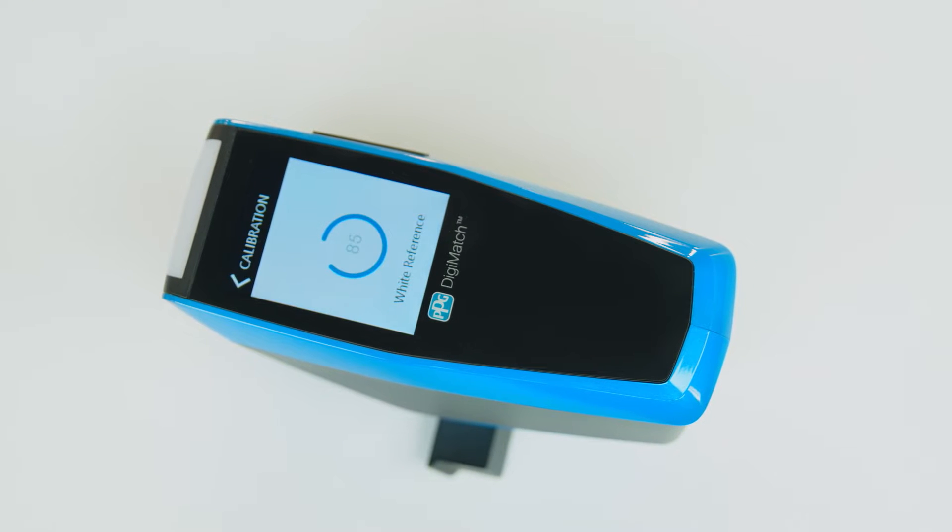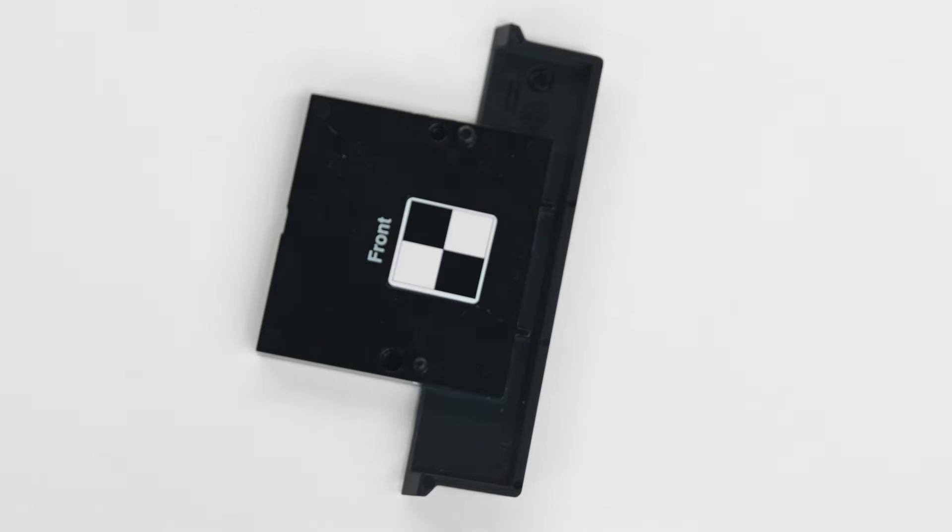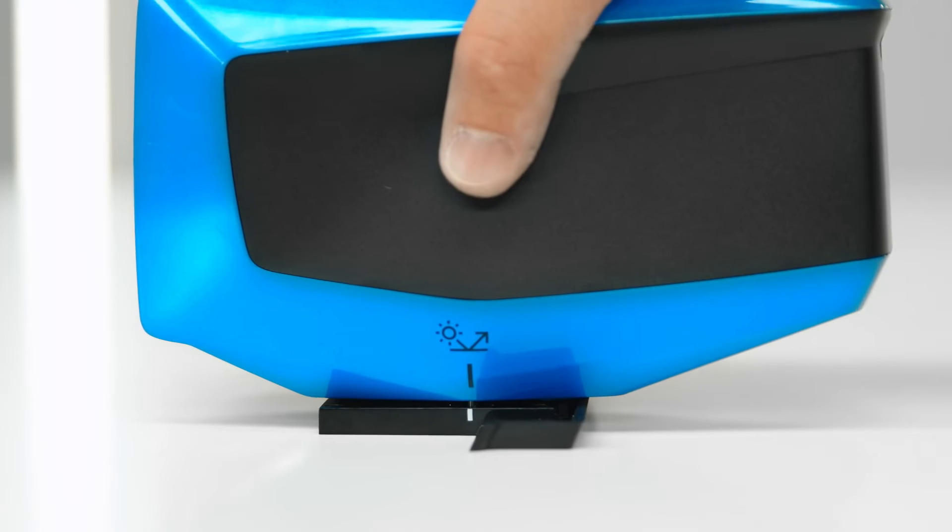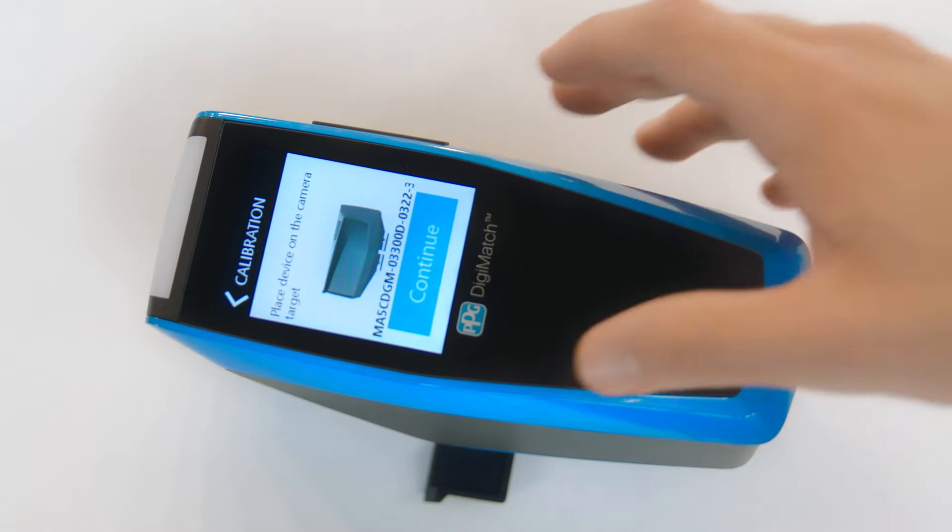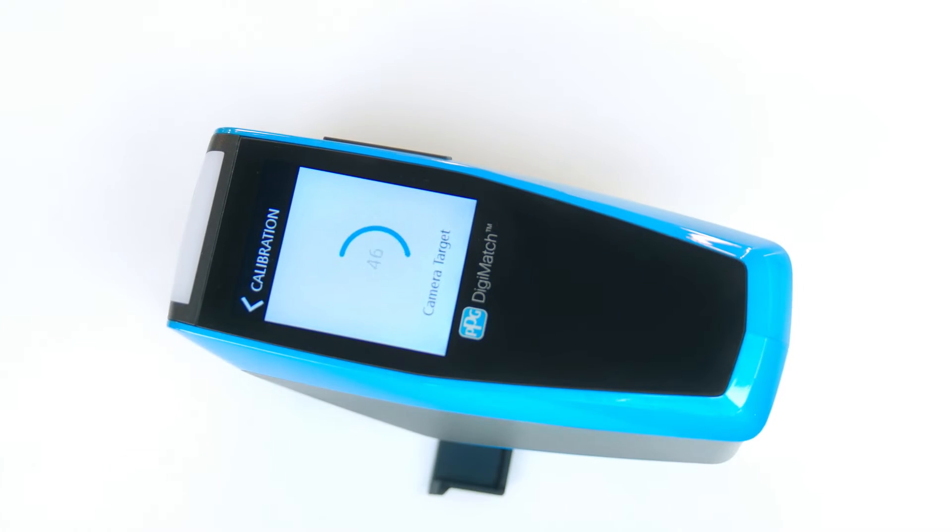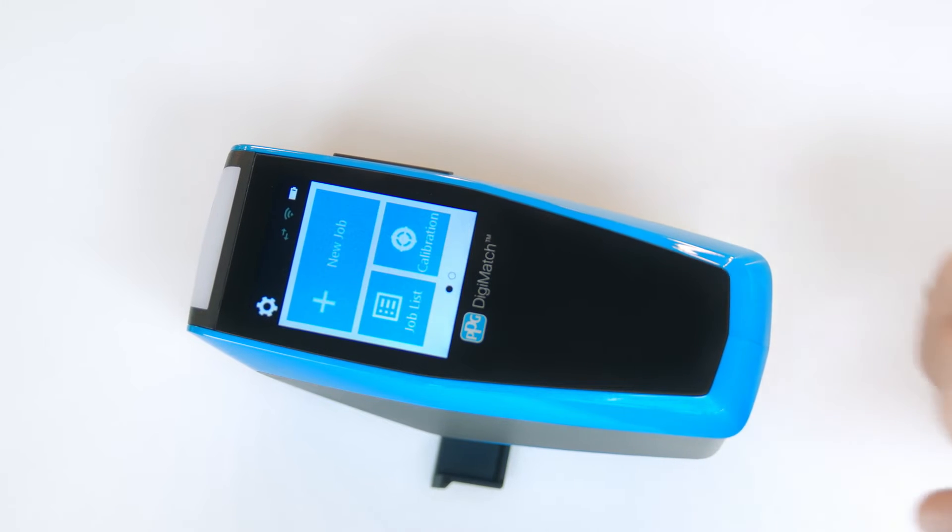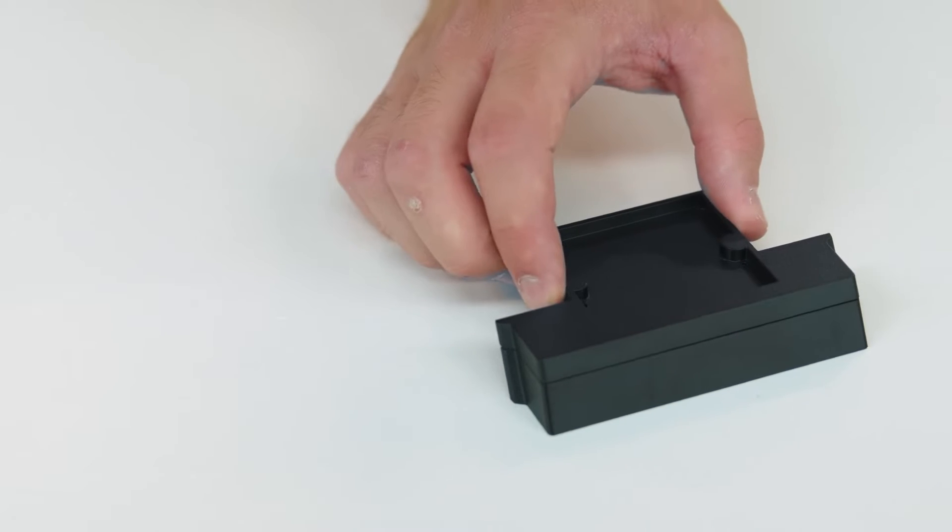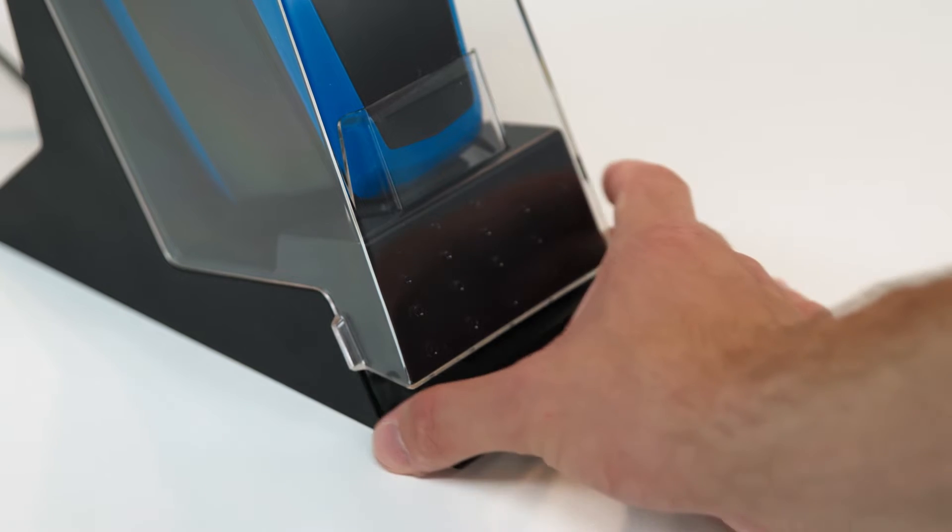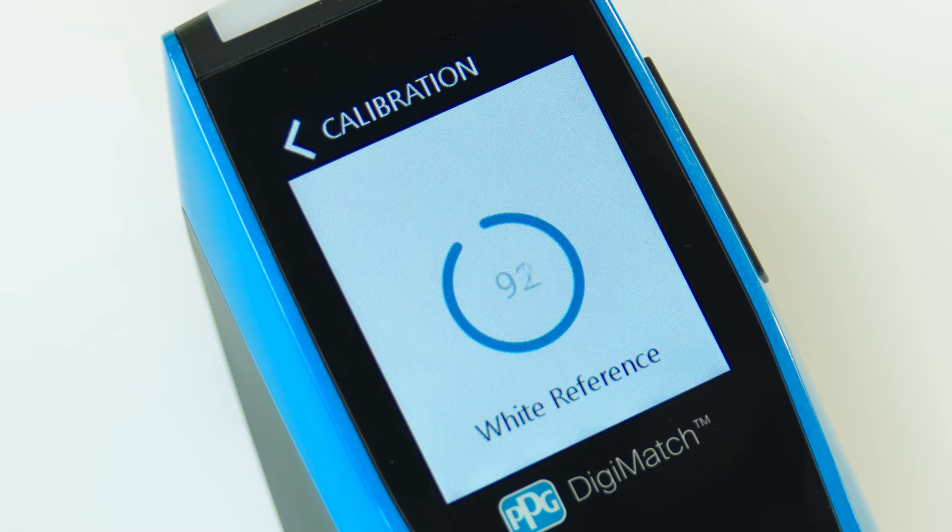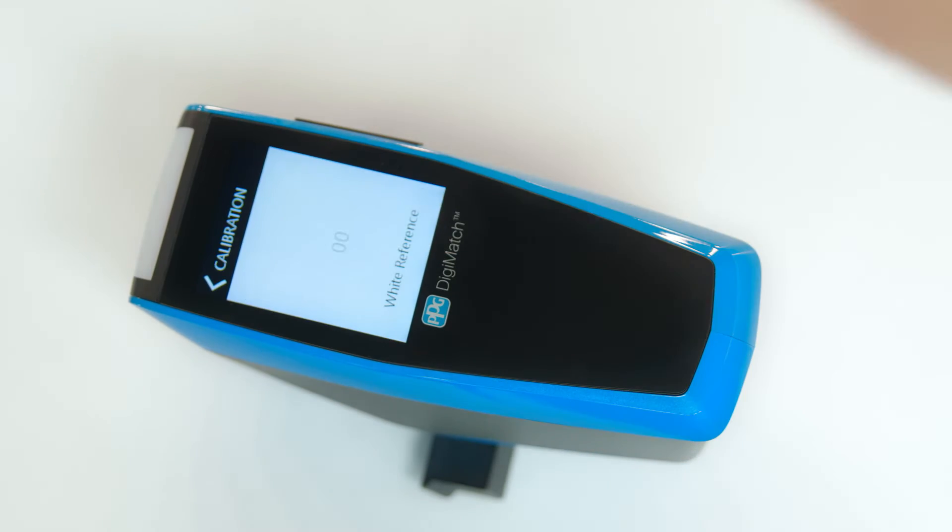Next, perform similar steps for the camera calibration. Position the device over the camera target tile, which is the black and white tile, again ensuring alignment. Click continue. The calibration tiles are severely affected by smudge marks, dust, and fingerprints. Make sure that your tiles stay clean by keeping them together and store them within the docking station. If you get an error message, you may need to wipe off the tile and perform that calibration again.